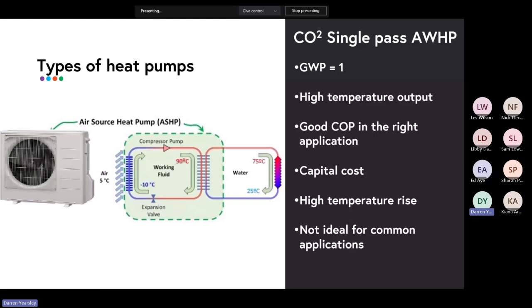And so that allows you 1,000 litres of reasonably cold water, which you can still run through your heat pump, get a reasonably good COP. But as that system now starts to recover and get back to 65 degrees, then you're compressing the delta T across the appliance. You'll still be delivering at 70 degrees, but you won't be getting a 50-degree rise anymore, because now you've got 30, 40, 50-degree water going back to your heat pump, and the efficiency is going down and down and down.